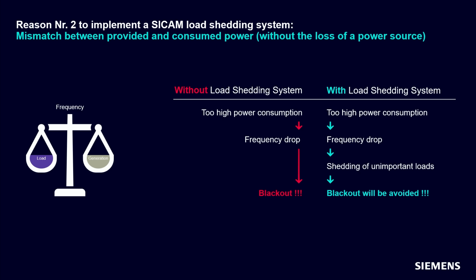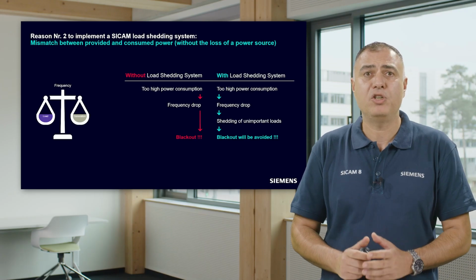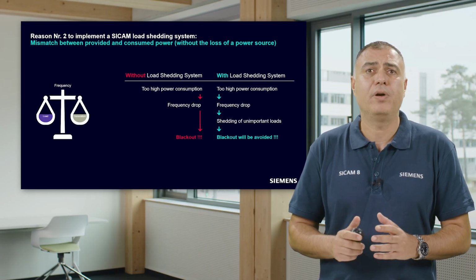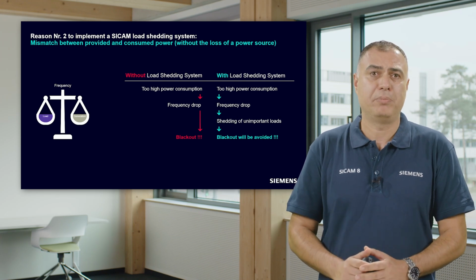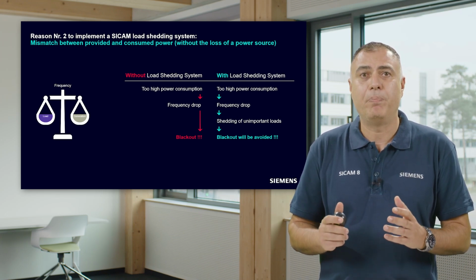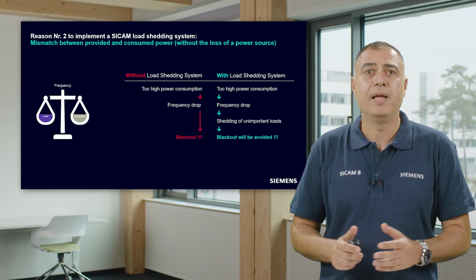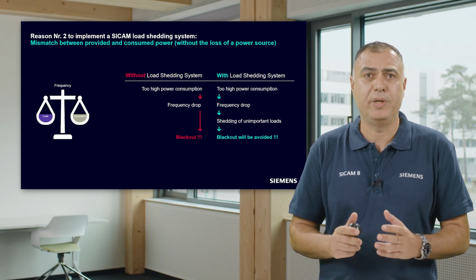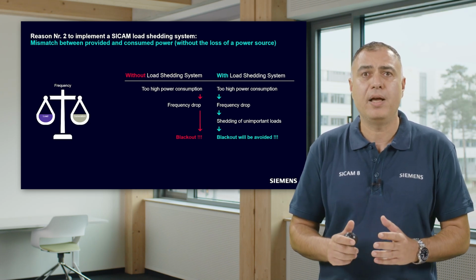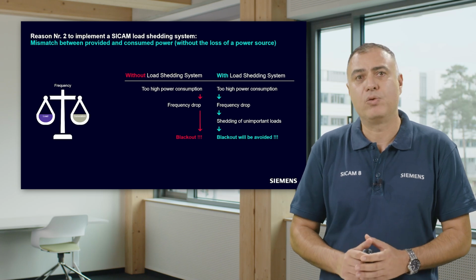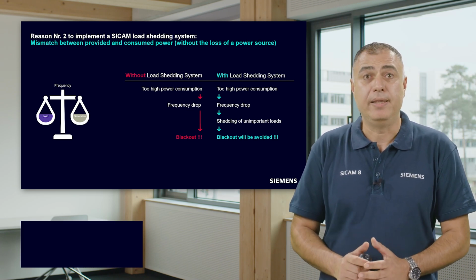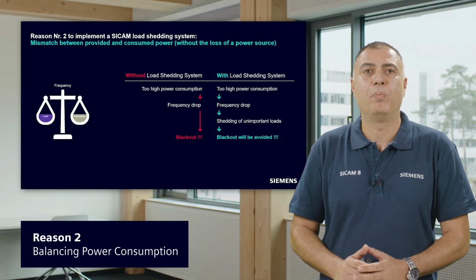Reason number two, also this is a typical use case. In many industrial applications, the different processes normally do not run simultaneously. For this reason, the power generators are not designed to cover the maximum possible power consumption. However, if the power restrictions are not observed and too many consumers are switched on, then there is no longer balance between available and consumed active power. In this case, again, a frequency drop will occur.